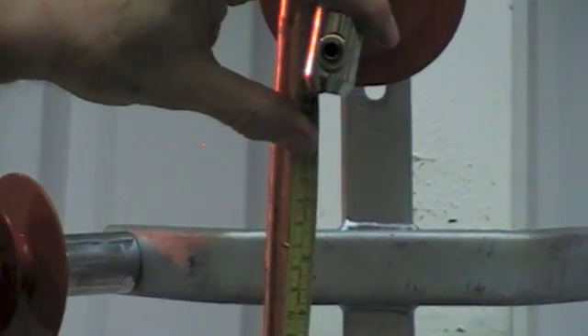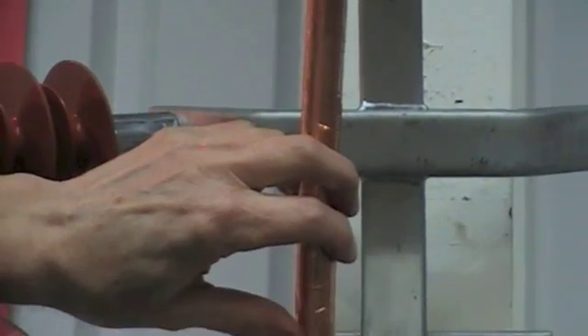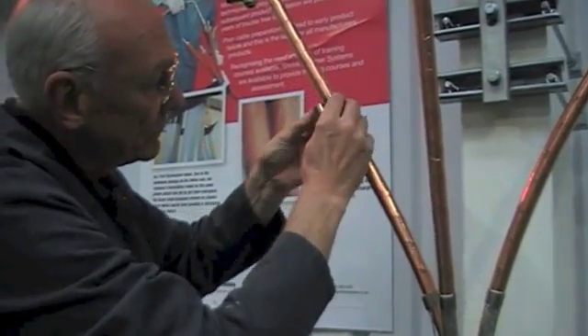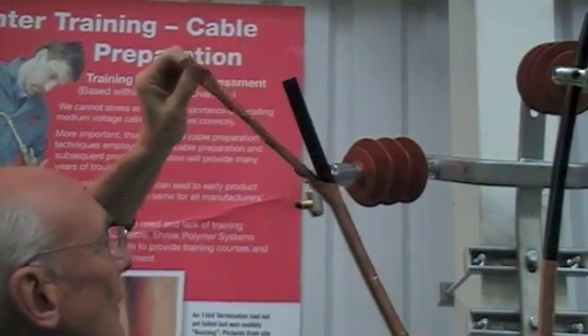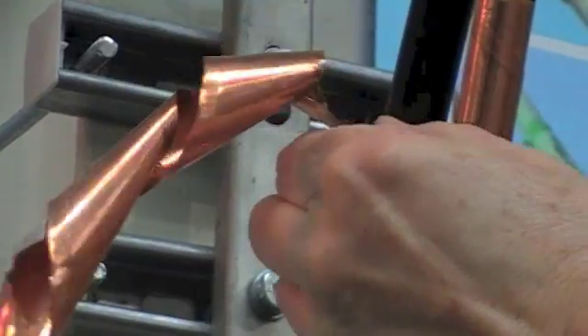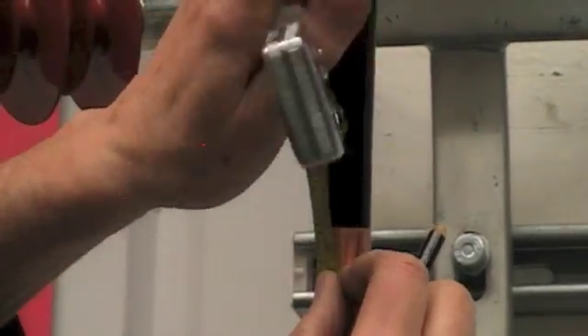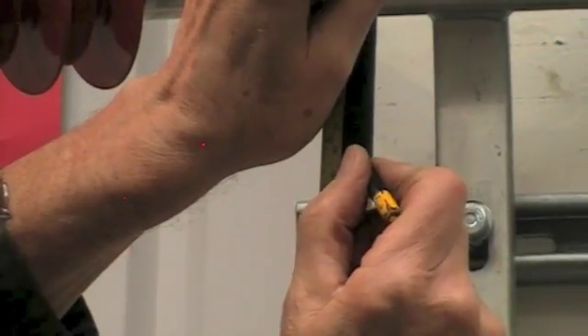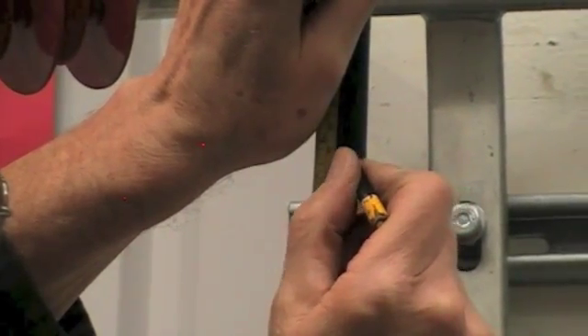Now mark out the lug barrel to the end of the semi-conductive screen point and mark the core. To facilitate the removal of the copper tape screen, you can apply a constant force spring and tear off to the edge. Now mark the screen end and apply some tape.